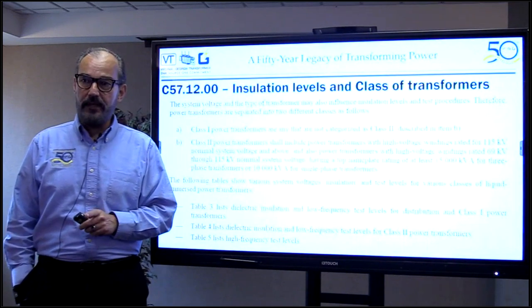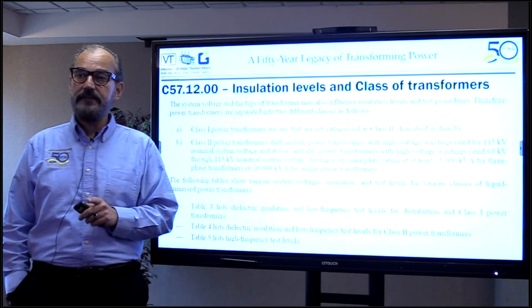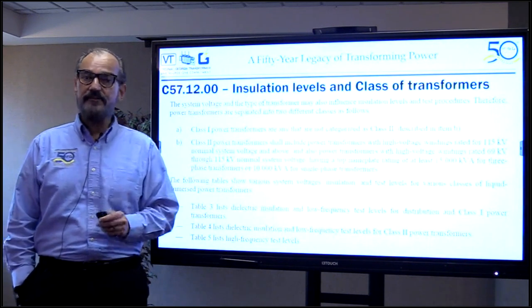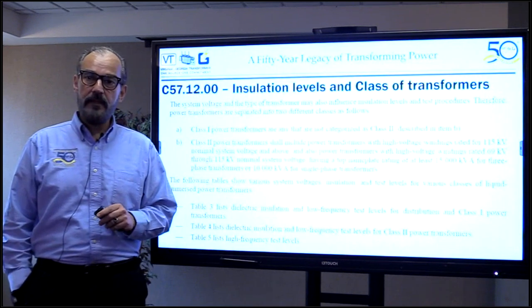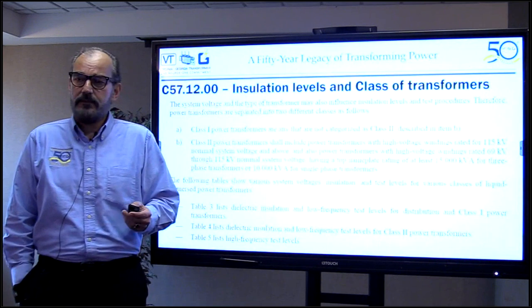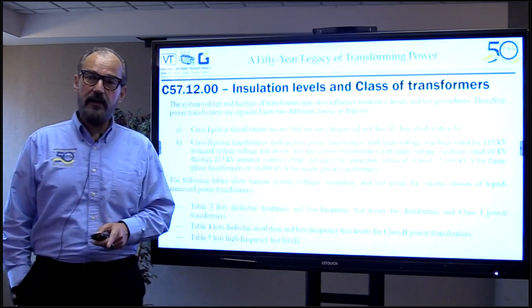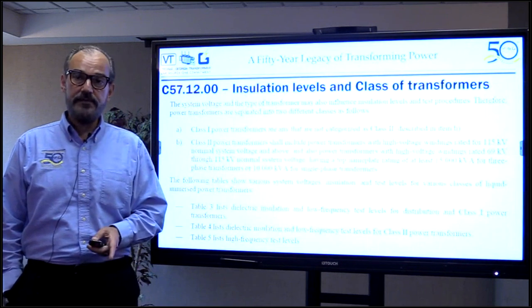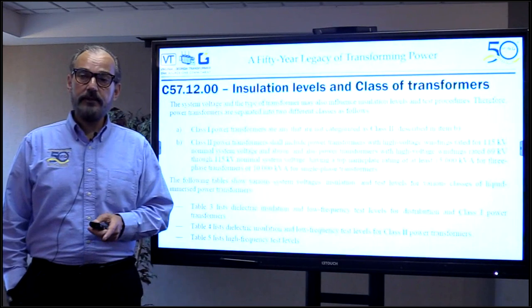The updated definition also includes power transformers with high-voltage windings rated 69 kV through 115 kV nominal system voltage, having a top nameplate rating of at least 15 MVA for three-phase transformers or 10 MVA for single-phase transformers. So a 69 kV, 25 MVA unit that was previously class one is now considered class two under the 2021 release. This is important from a testing perspective: the class defines what routine tests must be performed on your transformer, and what tests are designated as design tests.